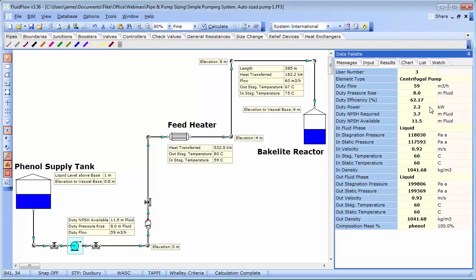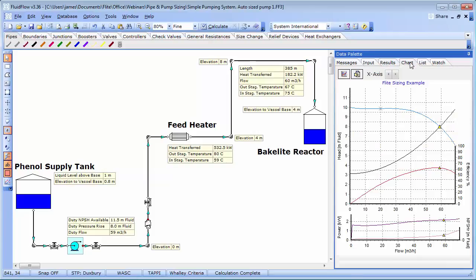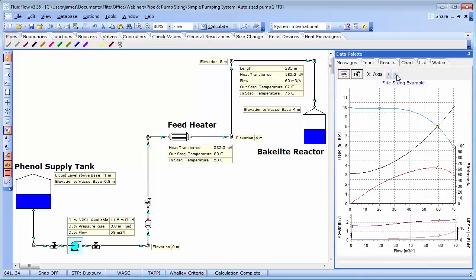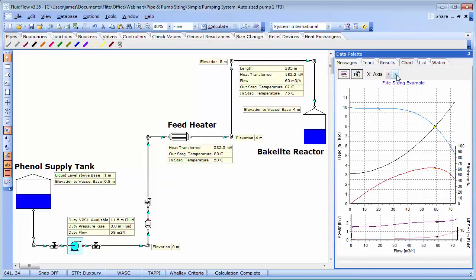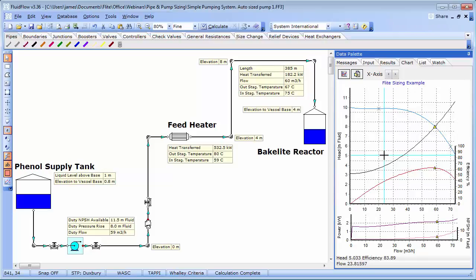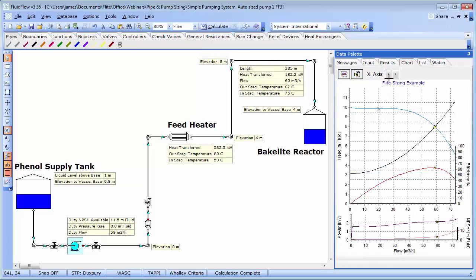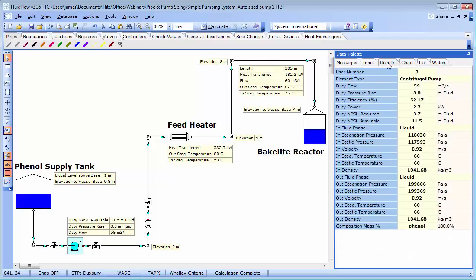We can also view the duty point on the pump curve, which helps us establish how close the duty point is to the best efficiency point. This particular system curve also shows the static head requirement arising from the elevation difference between the supply and delivery liquid levels. You might note that we need to deliver slightly more flow from the pump than we have solved in this case. Let's set about increasing the pump speed to match our design requirement.